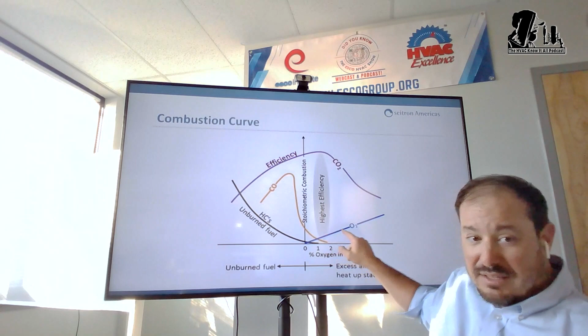So for those that work on large burners, if your oxygen's too high and your air is adjustable, that's probably one of the reasons why, right? Yeah, absolutely. Whatever you're using to adjust your air is open too much, maybe. Absolutely, and you just said exactly what our industry says all the time.